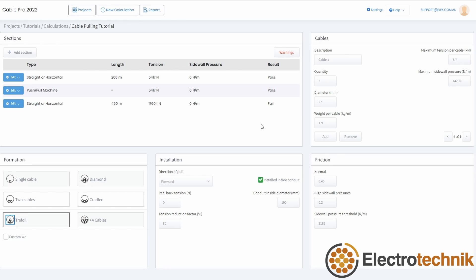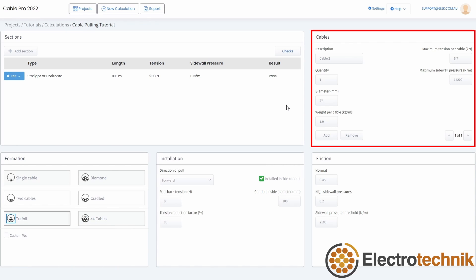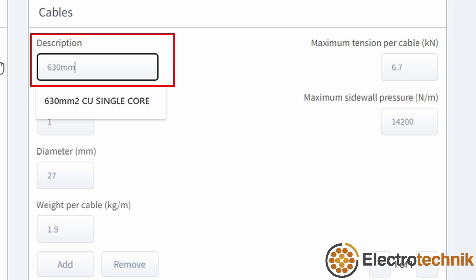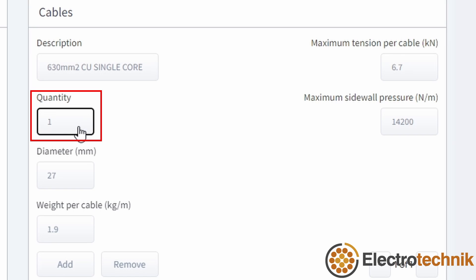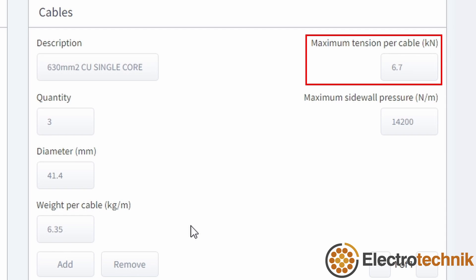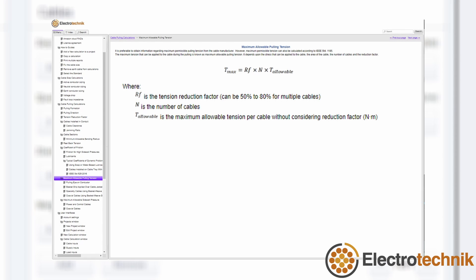Next, let's look at the inputs for the cables. All the cable types in the pull need to be entered here, including their quantities. For each cable type, enter a description such as 630mm² copper single core to make cables easier to identify. The quantity is the number of cables of that type which will be in the pull. The diameter and weight per cable are taken from the cable datasheet — take care to match the units of the inputs. The maximum tension per cable should be taken from the manufacturer, and often it will be on the cable datasheet or in their documentation. You can also calculate the maximum allowable tension of a cable if you can't get the actual value from the manufacturer; there is a section in the help manual called maximum allowable pulling tension which gives guidance on this.